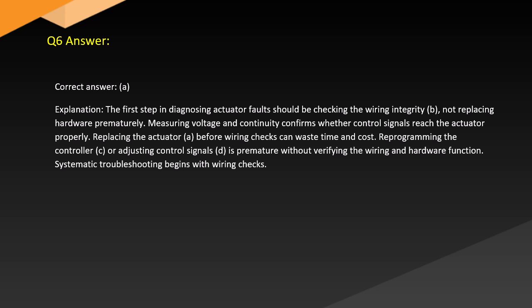Answer. Correct answer: B. Explanation. The first step in diagnosing actuator faults should be checking the wiring integrity, not replacing hardware prematurely. Measuring voltage and continuity confirms whether control signals reach the actuator properly. Replacing the actuator (A) before wiring checks can waste time and cost. Reprogramming the controller (C) or adjusting control signals (D) is premature without verifying the wiring hardware function. Systematic troubleshooting begins with wiring checks.